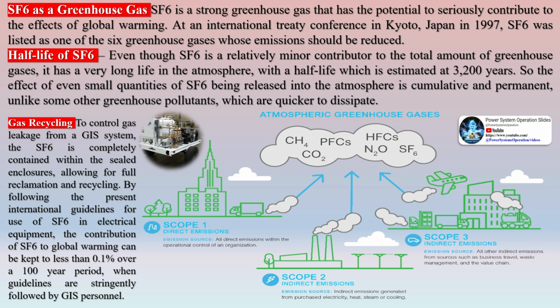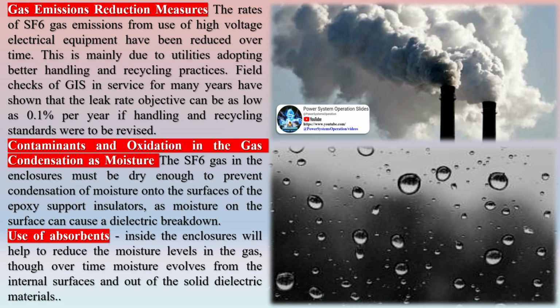By following the present international guidelines for use of SF6 in electrical equipment, the contribution of SF6 to global warming can be kept to less than 0.1% over a 100-year period, when guidelines are stringently followed by GIS personnel. The rates of SF6 gas emissions from use of high-voltage electrical equipment have been reduced over time. This is mainly due to utilities adopting better handling and recycling practices. Field checks of GIS in service for many years have shown that the leak rate objective can be as low as 0.1% per year if handling and recycling standards were to be revised. The SF6 gas in the enclosures must be dry enough to prevent condensation of moisture onto the surfaces of the epoxy support insulators, as moisture on the surface can cause a dielectric breakdown.